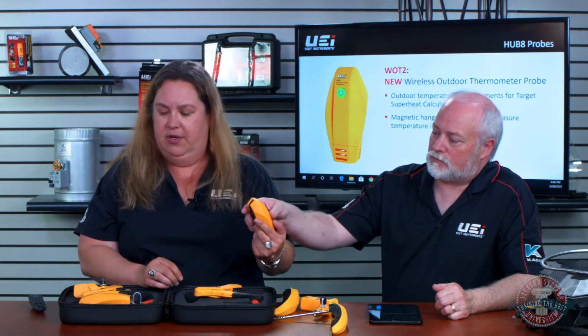And Mark, do you want to talk a little bit more about why that outdoor temperature probe is important? Yeah, depending on what type of system you're working on, sometimes you're going to charge by subcooling. If it's a fixed metering device or a refrigeration system, not just residential air conditioning, you want to know that superheat to make sure you're protecting that compressor from any flood back. So when we put this outdoor sensor outside, we get that ambient temperature, which can affect your target superheat temperature. So it's going to give that calculation for you inside the app and save you some time.